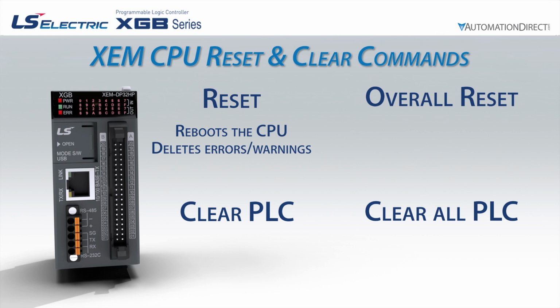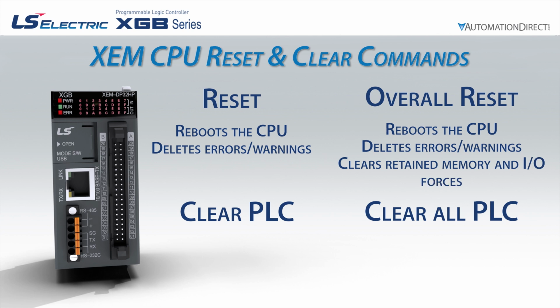The overall reset command performs a reboot of the PLC, clearing error and warning information, as well as clearing the retained memory and any forced I/O. The clear PLC command allows the programmer to select which sections of the PLC will be cleared. The user can clear configurations, programs, or specific memory locations from the CPU with this command.